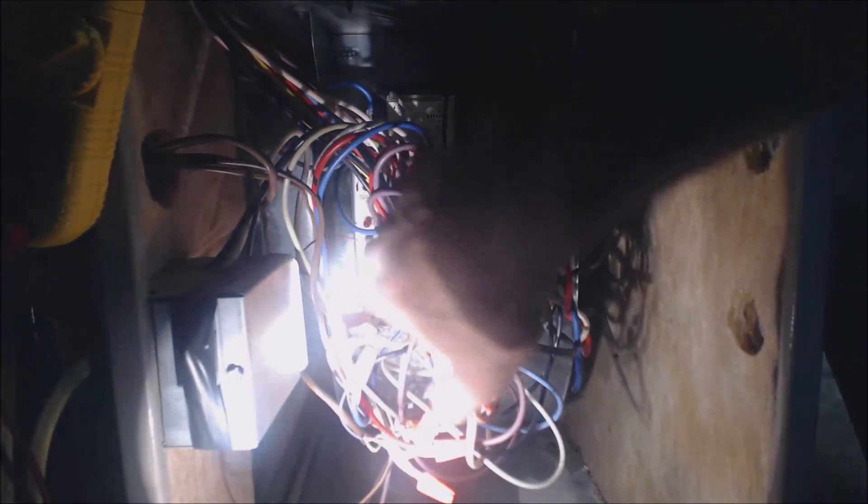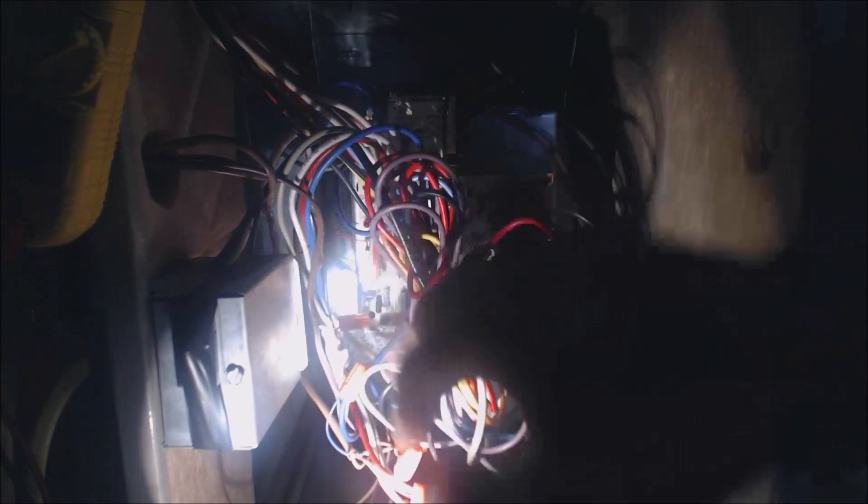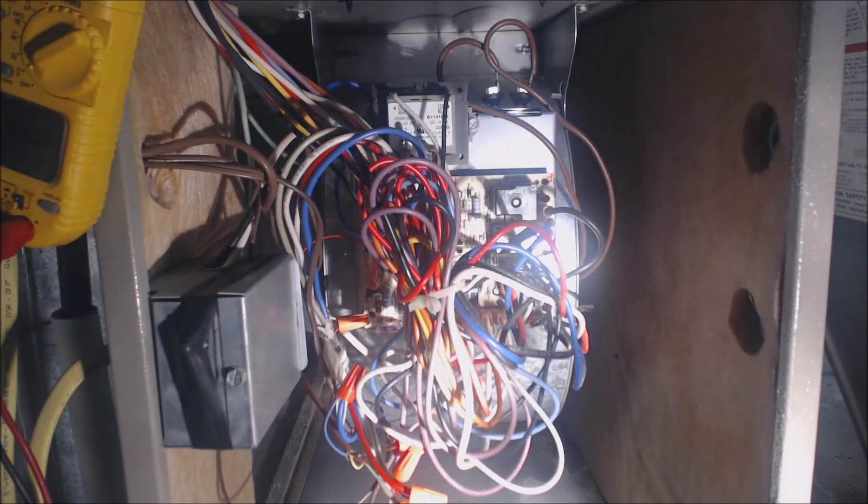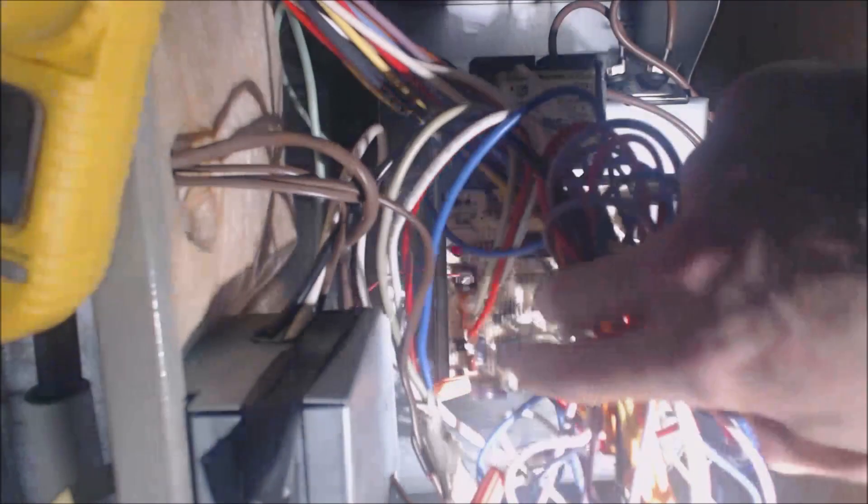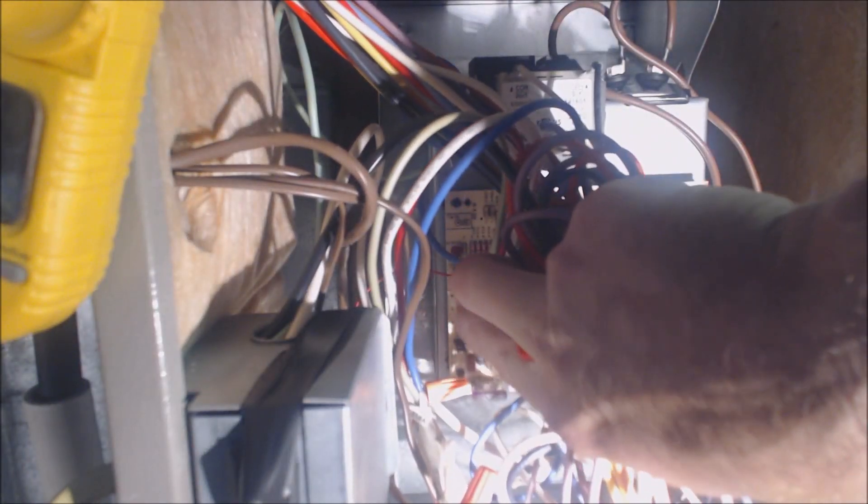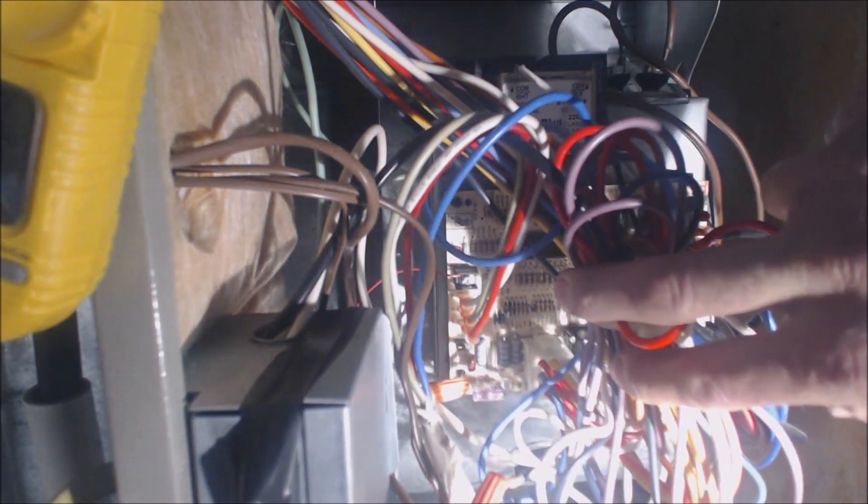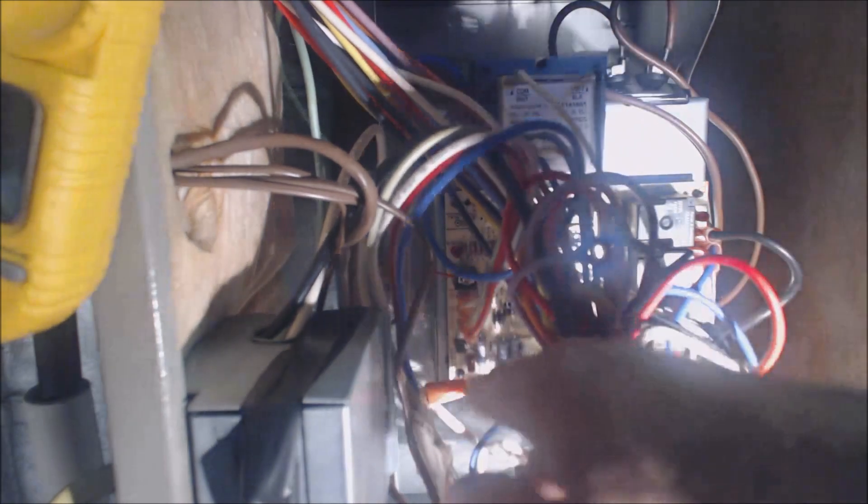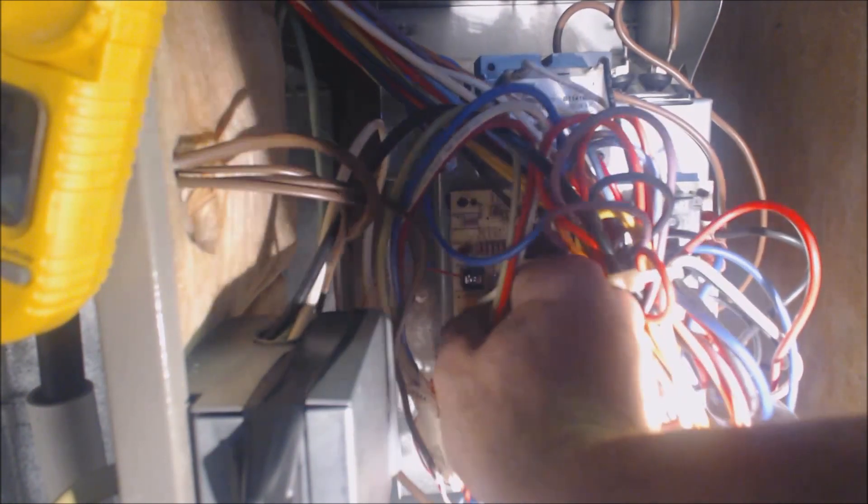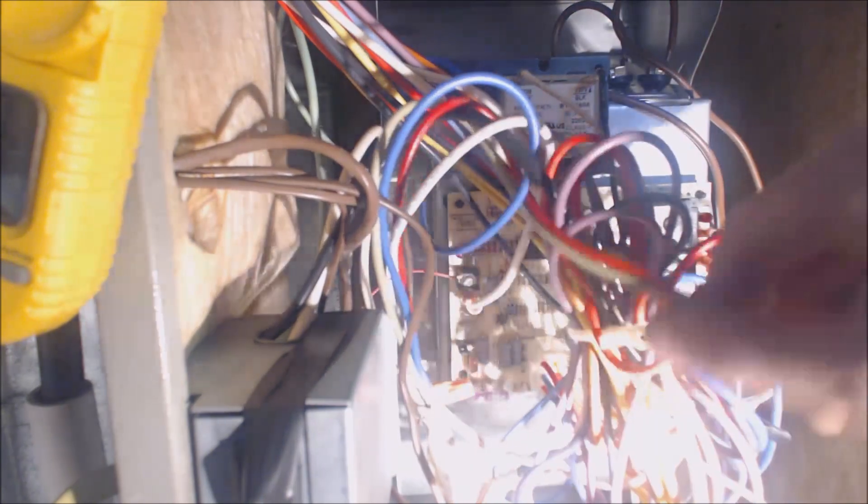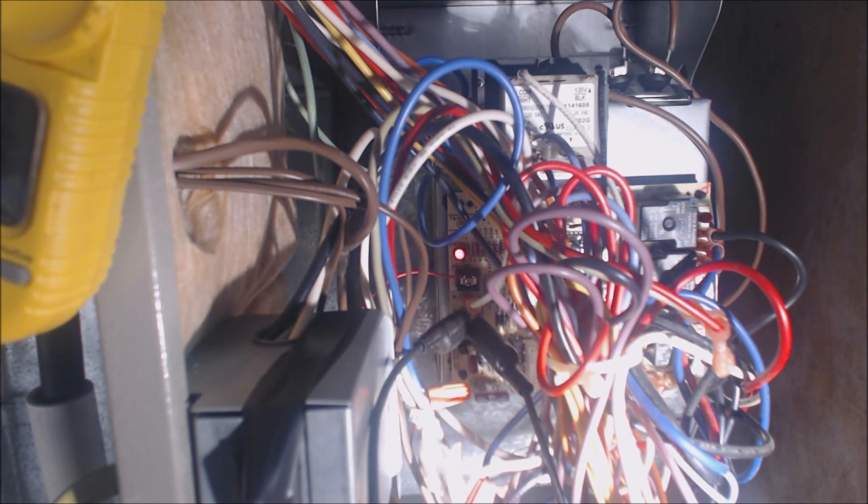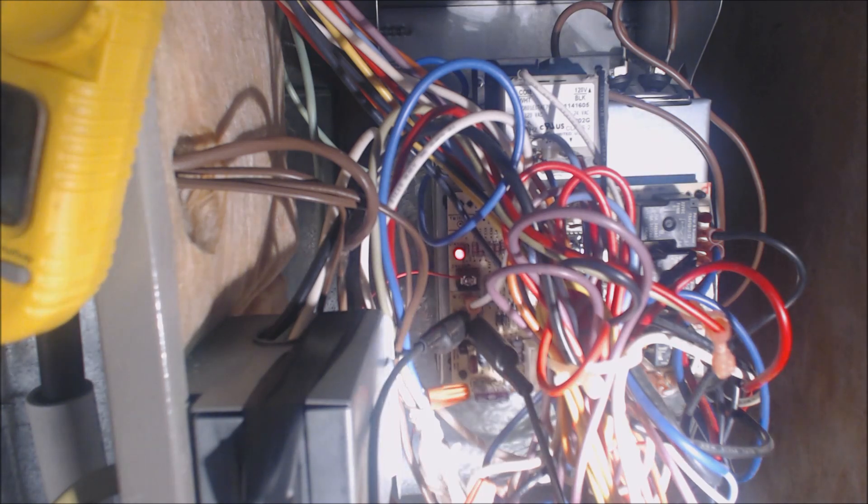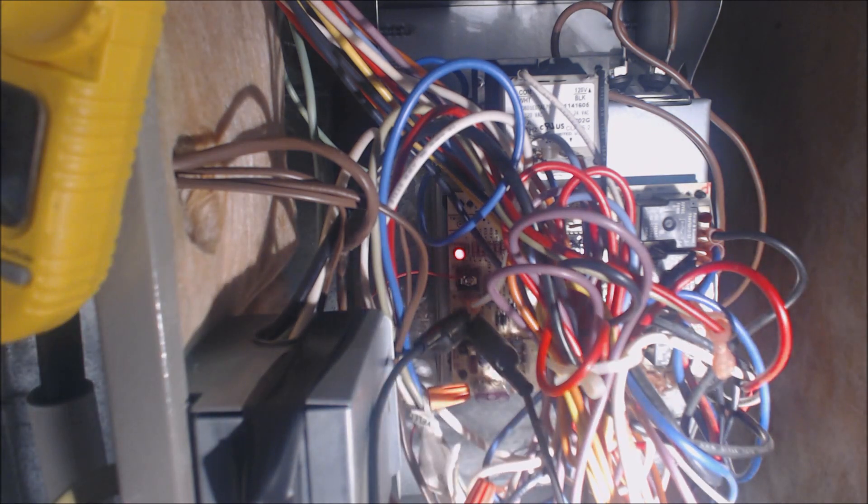This particular one has spade terminals where the thermostat wires are going. With the power off, I'm going to pull the red and the green. We can either take a voltage reading between green and common to see if the thermostat is calling the fan to turn on, or we can just go ahead and jumper R to G. Turn the unit back on. The unit is on and we should be calling for the fan. You just heard the click on the control board telling the blower motor to turn on.